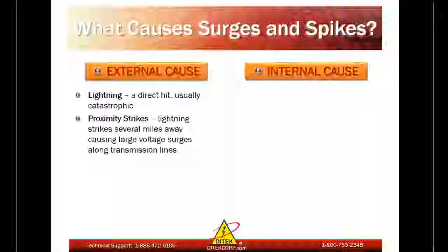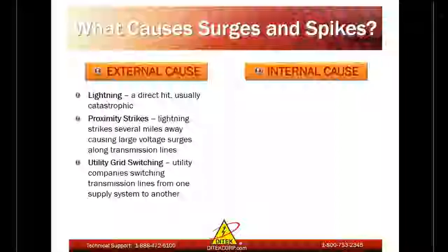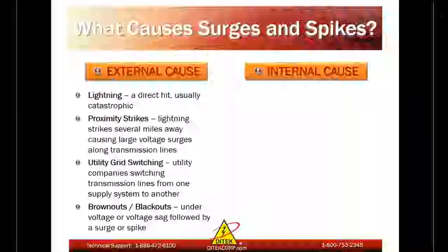We fit nicely here in proximity strikes, where the lightning strikes several miles away and can travel through the ground or aerial transmission lines into your equipment. Utility grid switching: this is when the utility companies switch the transmission lines from one supply system to another. And then brownouts and blackouts, which are typically a sag in voltage or a voltage outage, followed by a surge or a spike.